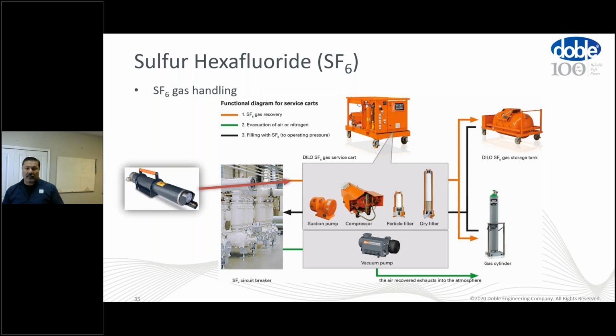Or if it's a GIE that's been in service for some time, I highly, highly recommend that you use a pre-filter in place. This is really important. Again, you're introducing this vapor that may have contamination through a number of components, including the vacuum pump, including the compressor, including the filters and your hoses and accessories. So having that pre-filter in place is going to make sure that you're not going to cross-contaminate, and you're going to end up with a material at the end that you'll be able to reuse. So you'll be able to recover, recycle, and reuse.